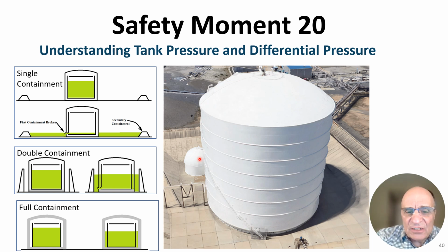Now, this tank that's shown here is a special kind of tank. There aren't too many of this type of tank, in that you see there's a special breather tank here. In this tank, there's an annular space that's filled with nitrogen. And this breather is nothing more than a bladder with a weight on top of it that allows that barometer change to keep this nitrogen pressure at a fixed differential between the barometer and the annular space. Now, look at these single containment, double containment, and full containment tanks that I show here. The annular space is filled with boil-off gas. And inside this annular space would be insulation. And we'll talk in more detail about how much insulation and what kind of insulation is used there.